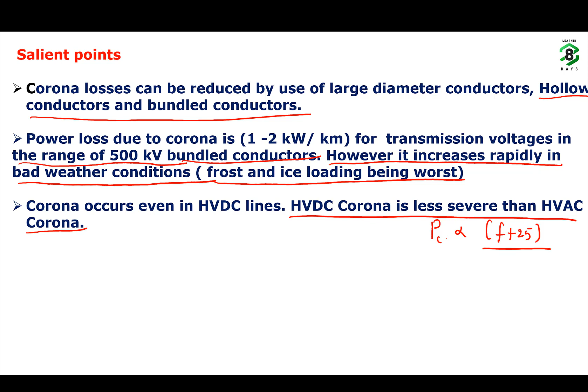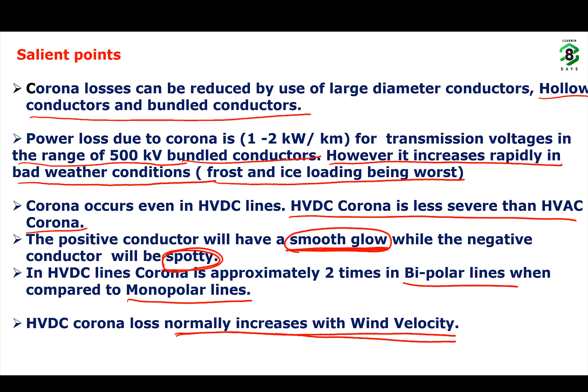The next point is the positive conductor in HVDC lines will have a smooth glow. The positive polarity conductors in HVDC lines will have a smooth glow, while the negative conductor will have a spotty glow. In HVDC lines, corona is approximately 2 times in bipolar lines when compared to monopolar lines. That means corona in monopolar lines is less when compared to the corona in bipolar HVDC transmission lines. Corona in HVDC transmission lines normally increases with the wind velocity. You remember these points.